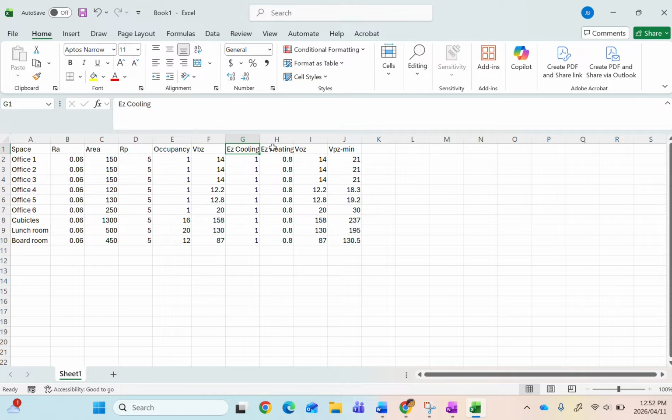And I'll just show you what this formula looked like written out again. It looks a little bit different in Excel, but I assure you these are the same things. So this gave us a VOU value of 302 CFM. So our last step is to calculate our VOT value, and that is just the VOU value divided by EV. And ultimately we get a VOT value of 522 CFM.